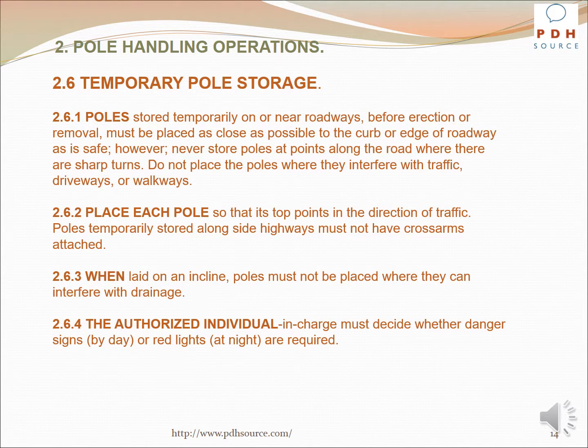Poles stored temporarily on or near roadways before erection or removal must be placed as close as possible to the curb or edge of roadway as is safe. However, never store poles at points along the road where there are sharp turns. Do not place the poles where they interfere with traffic, driveways, or walkways. Place each pole so that its top points in the direction of traffic.